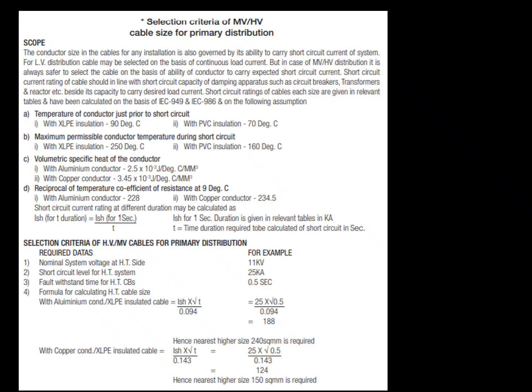Short circuit current rating of cable: 1. Temperature of conductor just prior to short circuit with XLPE insulation is 90 degrees Celsius. In case of PVC, it is 70 degrees Celsius. Maximum permissible conductor temperature during short circuit: for XLPE, it is 250; for PVC, it is 160. Volume specific heat of conductor, volumetric: with aluminum conductor, it is 2.5 multiplied by 10 raised to the power minus 3 joules per degree. With copper, it is 3.45.